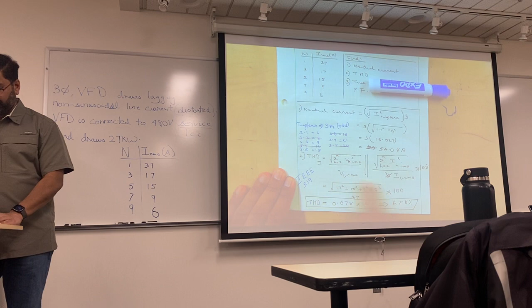This number tells me that this is a highly distorted current, because I have way too much. And the truth be told, it's because of this third harmonic and fifth harmonic being so high.